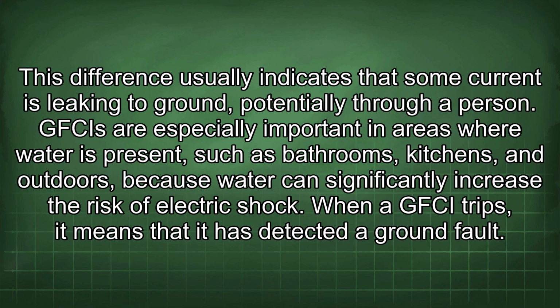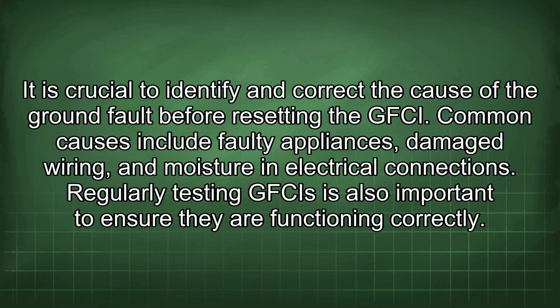GFCIs are especially important in areas where water is present, such as bathrooms, kitchens, and outdoors, because water can significantly increase the risk of electric shock. When a GFCI trips, it means that it has detected a ground fault. It is crucial to identify and correct the cause of the ground fault before resetting the GFCI. Common causes include faulty appliances, damaged wiring, and moisture in electrical connections.